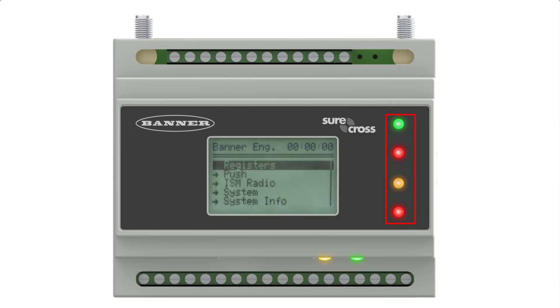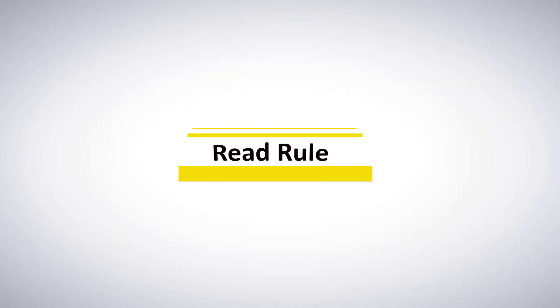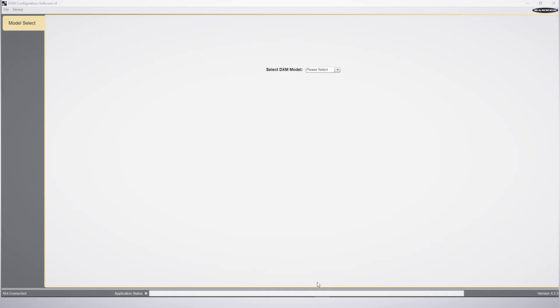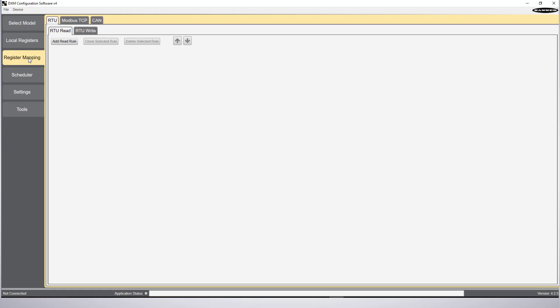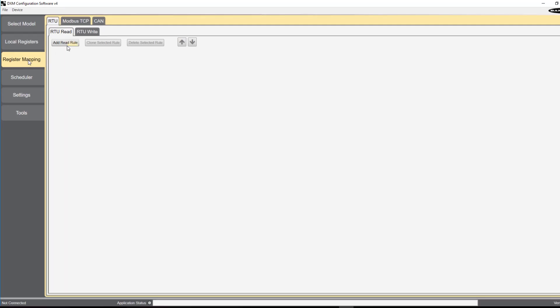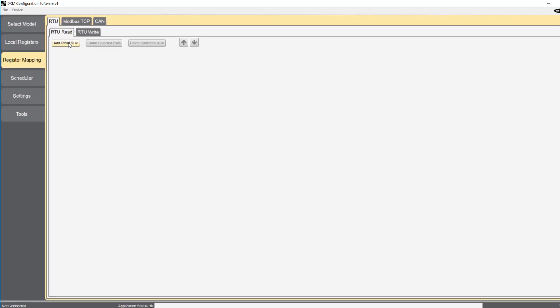In order to utilize the functionality of the DXM controller, we must first read data into the local register via a read rule. I'm connected to a DXM 700, so I'll select it in the software. You'll find the read rule under register mapping and RTU read.